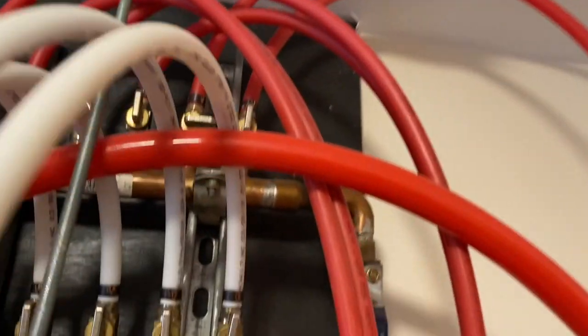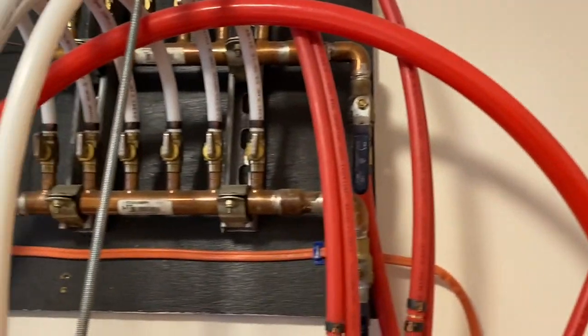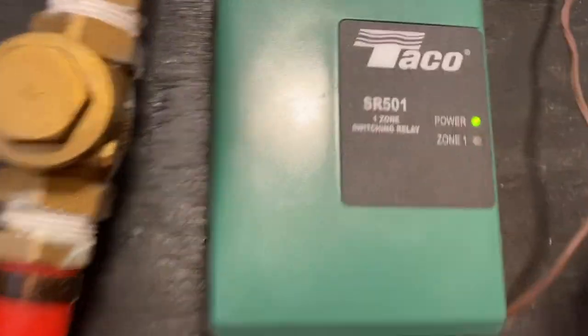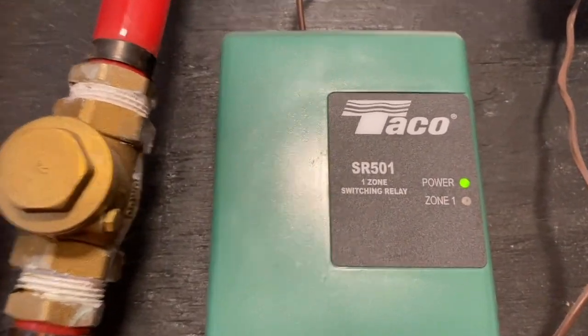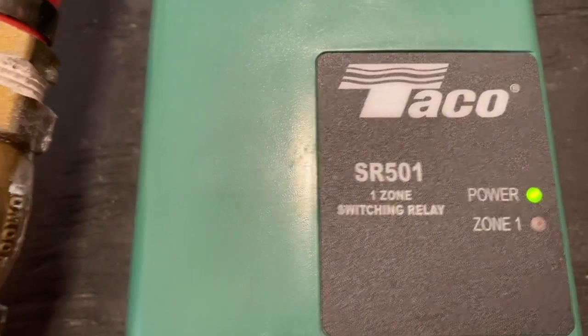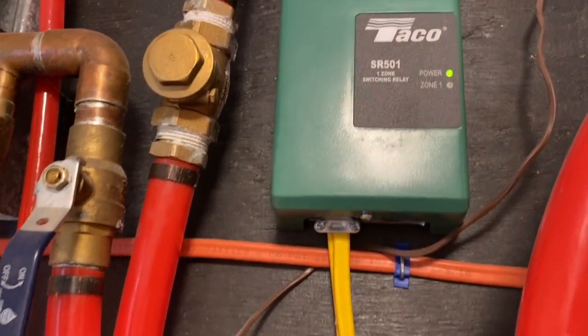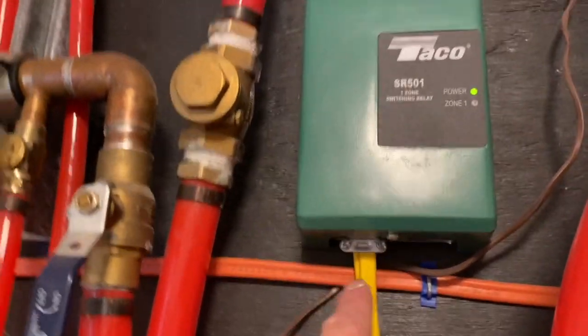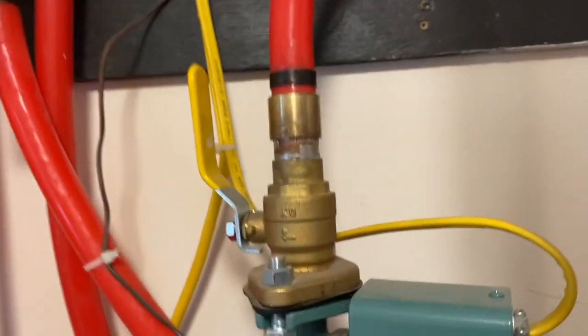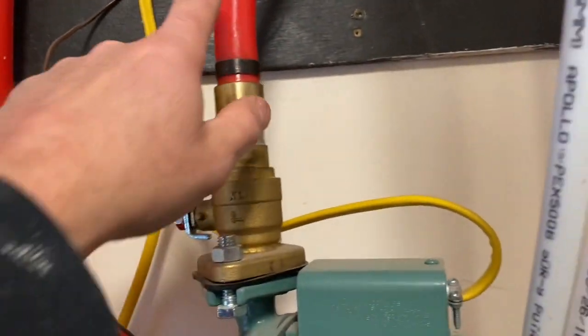The feed line goes up and ties in right there, which just supplies the system. This box here is 24 volts, which goes into a Taco SR501 one-zone switching relay. Right now it's not calling for heat — zone one would be red if it were calling. So 24 volts comes from the thermostat, sends a signal here, which goes into this pump — a Taco 009 double pump.